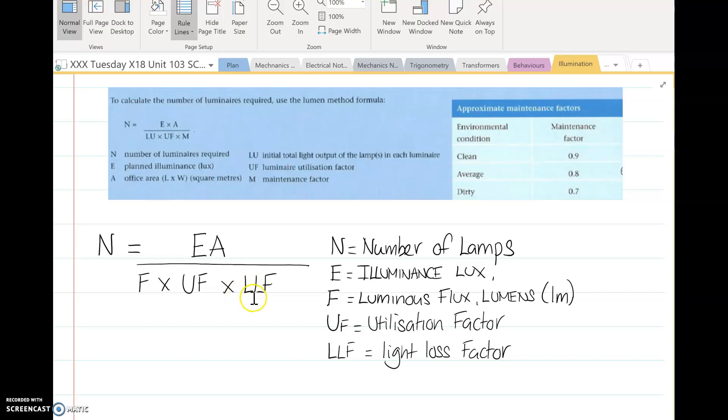So the light loss factor is also known as the maintenance factor, how often the lights are going to be cleaned. Typical factors: if it's a clean environment we can set that as 0.9, but if it's a very dirty environment then we can set that at 0.7. And what that does is that increases how many lights we need.